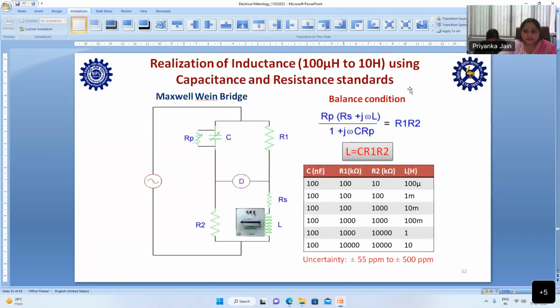And we have inductance measurement, which I have mentioned. We have the Maxwell bridge where we can define the inductance. We need a combination of resistance and capacitance to define the inductance. Here R1, R2 are standards, and C is also a standard, a variable capacitance: one standard capacitance connected with a variable capacitor. So it's a combination of a variable capacitor and a standard capacitor. When we balance the bridge, we have a known value of R1 and a known value of R2, but C is not fully known because we have one known C, that is our standard, and one variable part applied here.